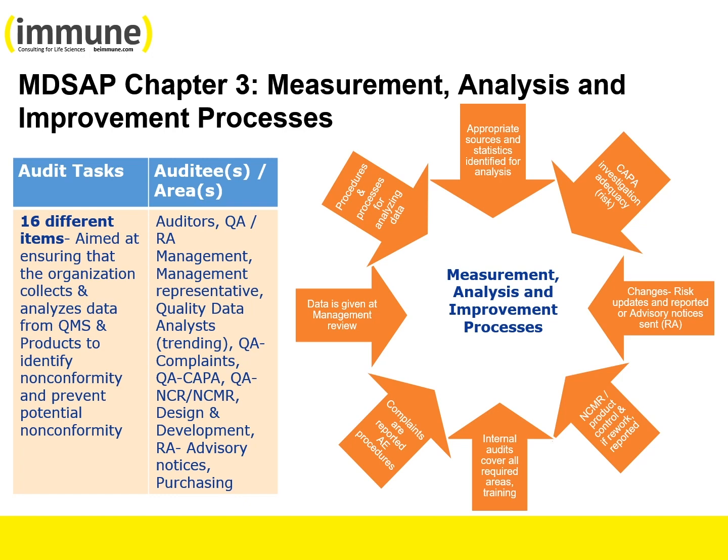Ensured investigations are conducted to identify underlying causes of nonconformities and potential nonconformities where possible. Implemented appropriate CAPAs to eliminate the reoccurrence or preventive action to ensure that quality problems do not occur. Review the effectiveness of corrective actions and preventive actions, and utilize information from the analysis of production and post-production quality data to amend the analysis of product risk as appropriate.